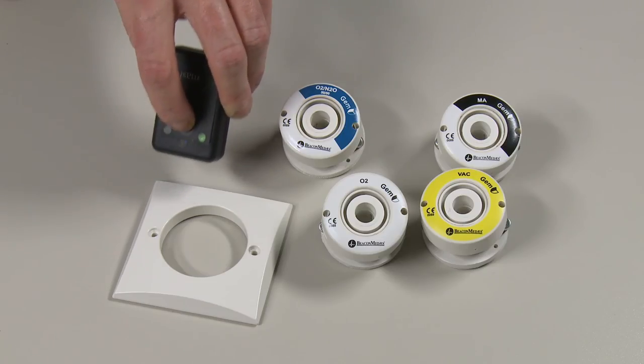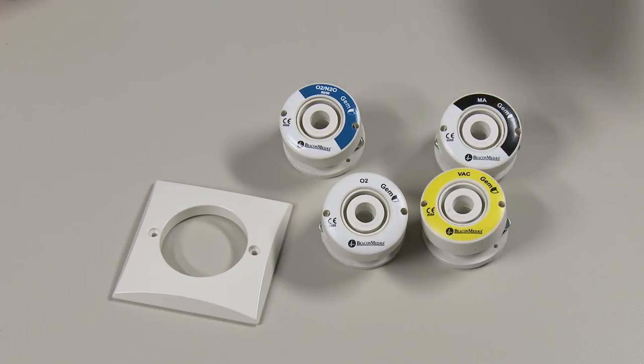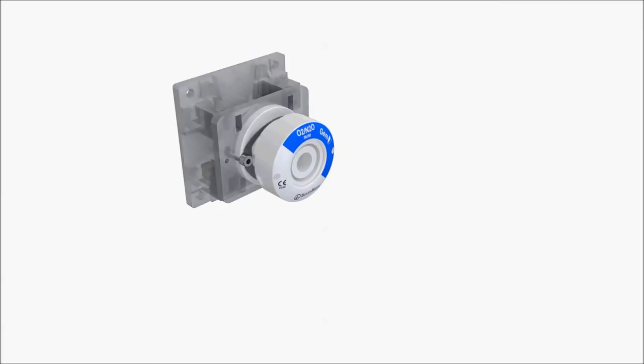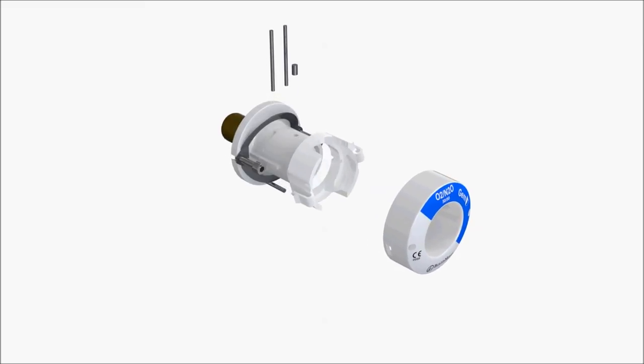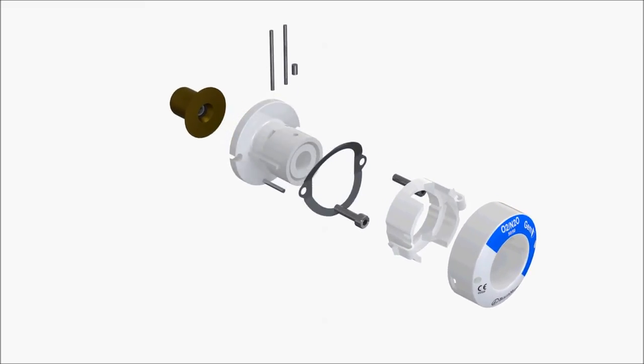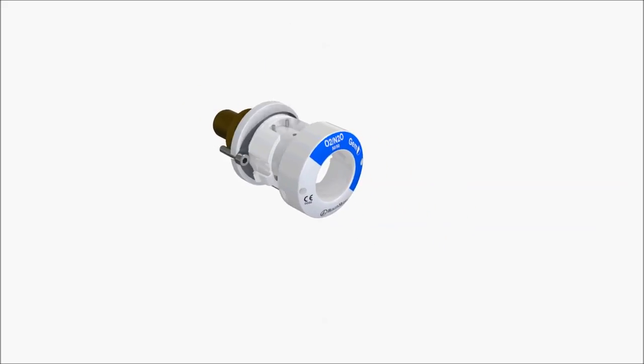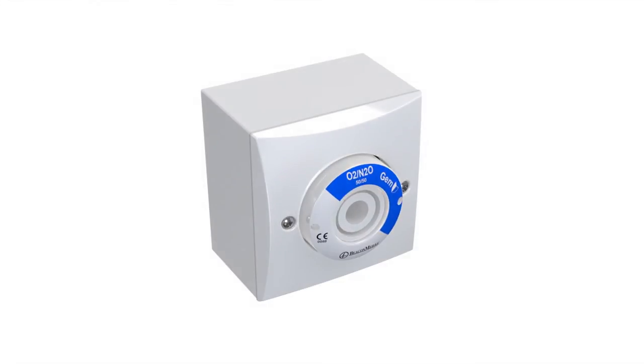This not only proves the antimicrobial properties but can ensure the outlet is a genuine Beacon Medaes product. Additionally, Beacon Medaes have kept the class leading internal check valve and first fix assembly from the current model, meaning backwards compatibility. Mark III and Mark IV outlets can be upgraded to GEM Shield in the field. Please contact your sales representative or service technician for more details.